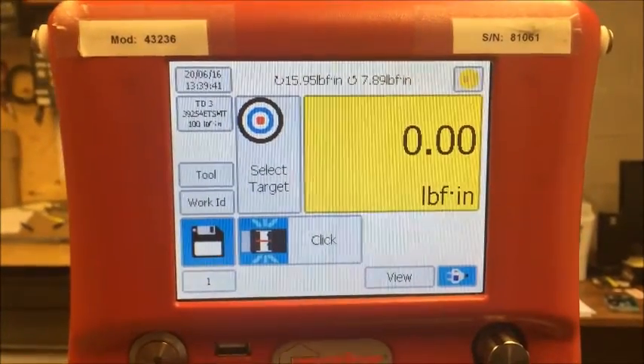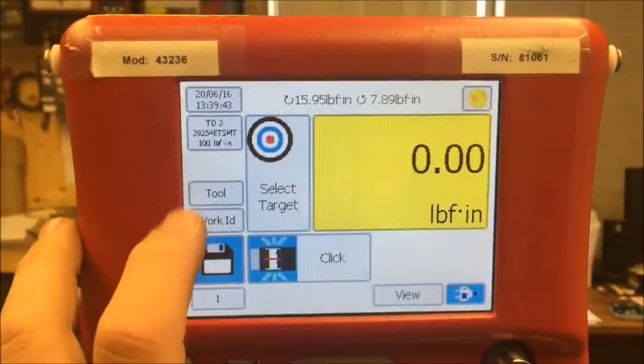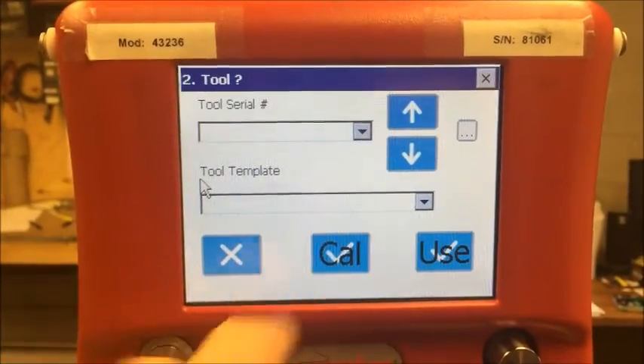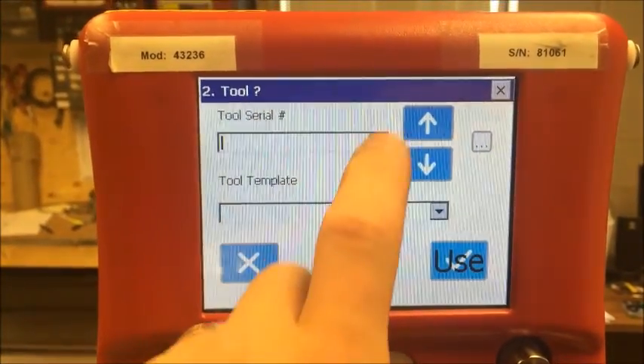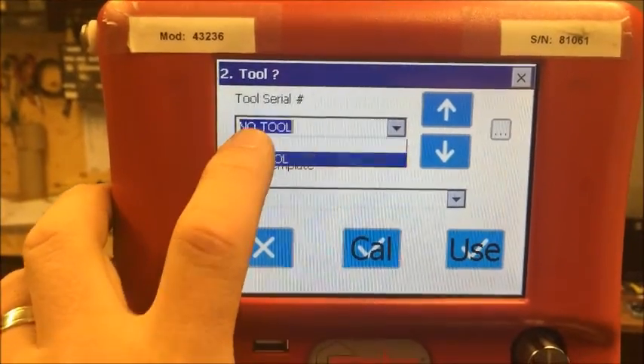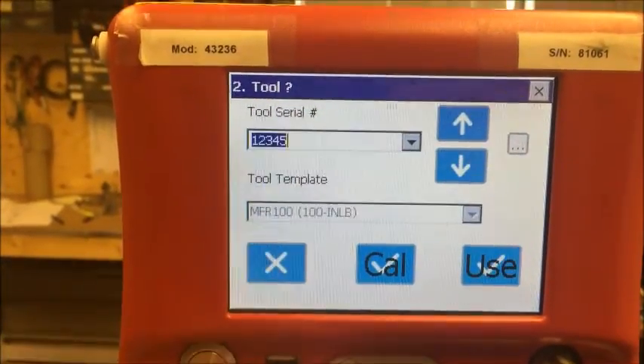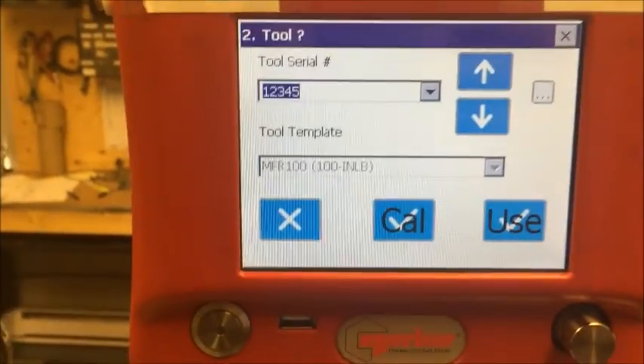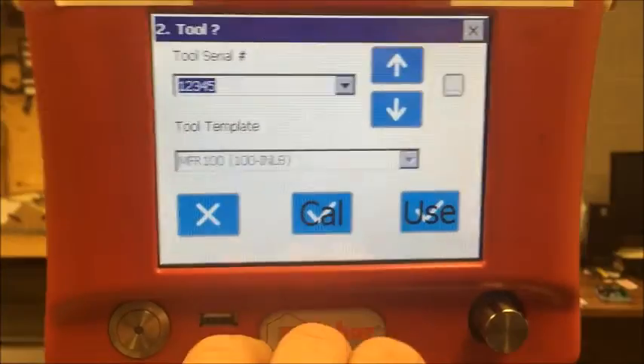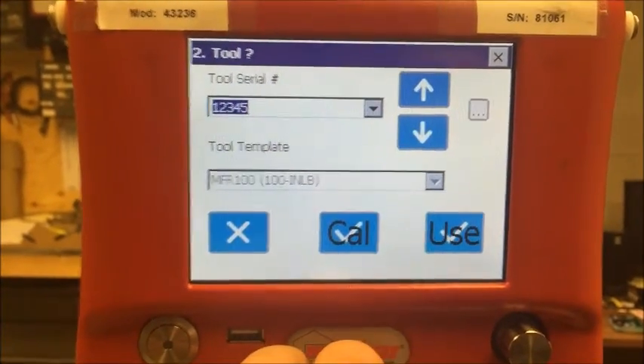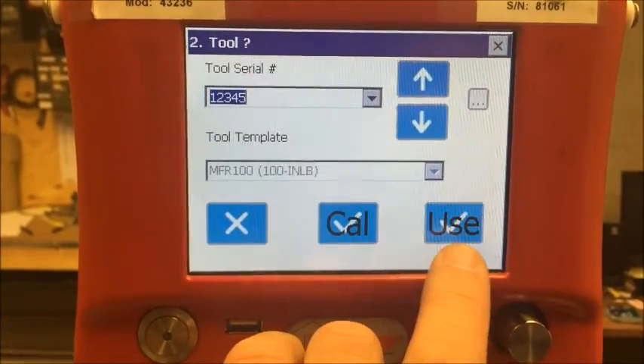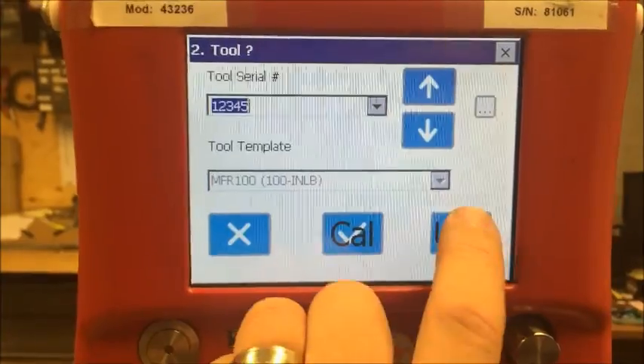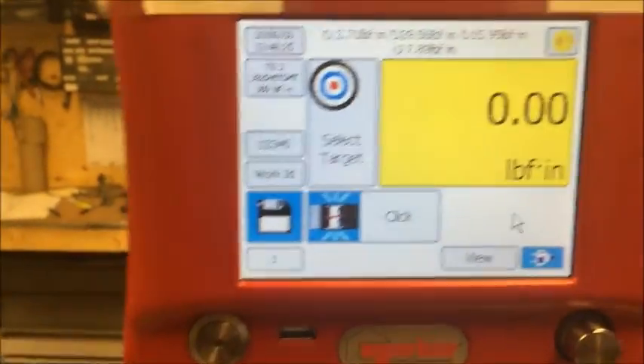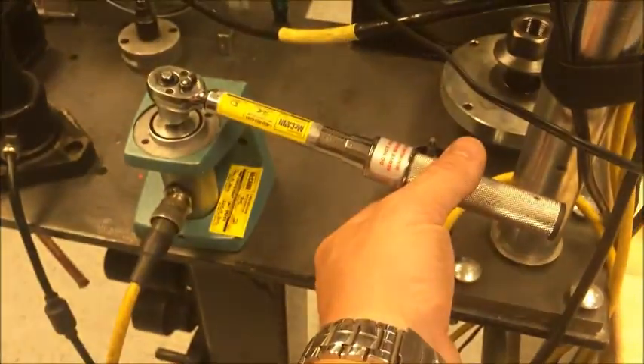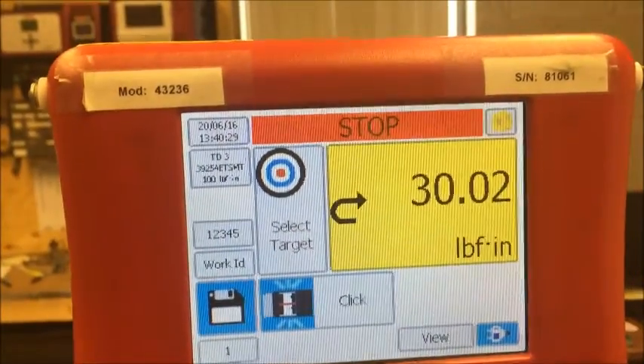So now we want to check a tool. Your technician comes in, the first thing he does is go tool to find the tool in the list. Pop the drop down box and you should see the tool I just created, 1, 2, 3, 4, 5 in the list. We can use it or we can calibrate it. The difference between use and calibrate is basically if we hit use, we can set the wrench to any setting we want, put it on our tester, and just see what we're getting.